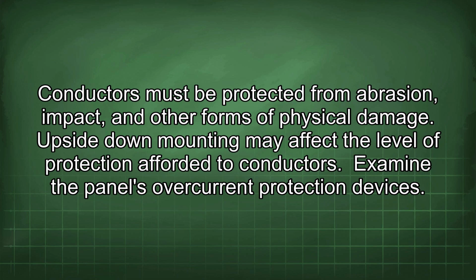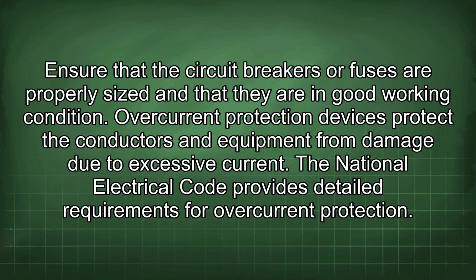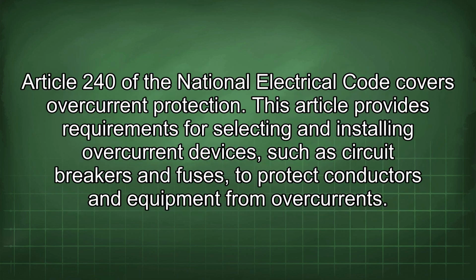Examine the panel's overcurrent protection devices. Ensure that the circuit breakers or fuses are properly sized and that they are in good working condition. Overcurrent protection devices protect the conductors and equipment from damage due to excessive current. The National Electrical Code provides detailed requirements for overcurrent protection. Article 240 of the National Electrical Code covers overcurrent protection.